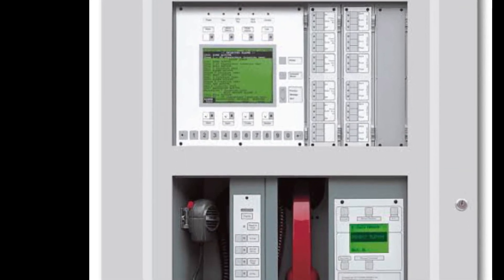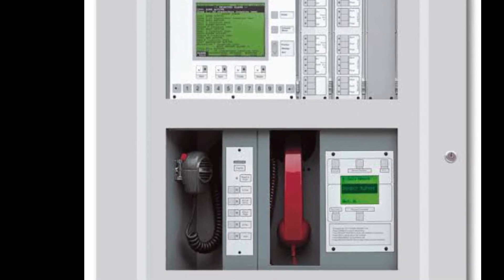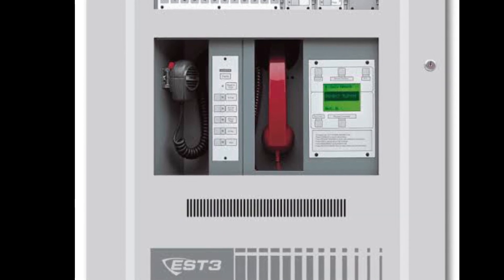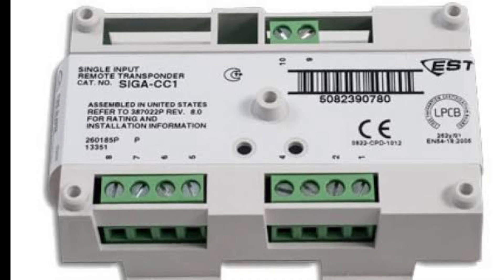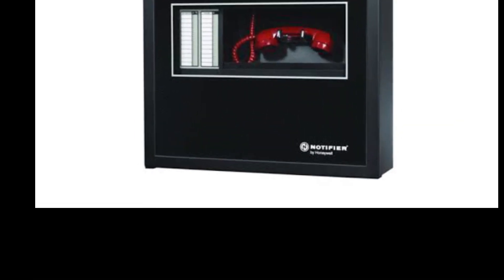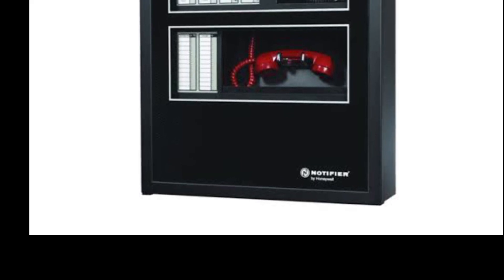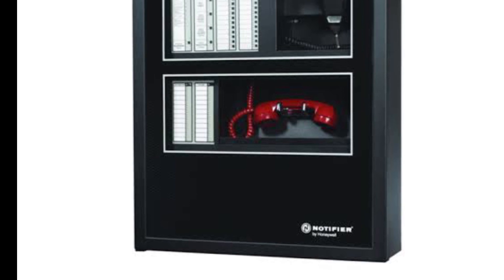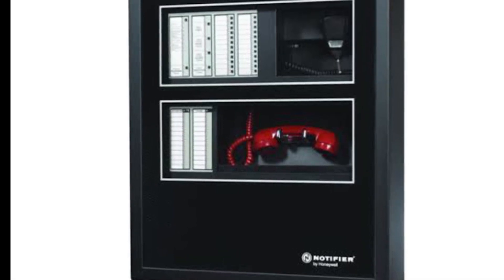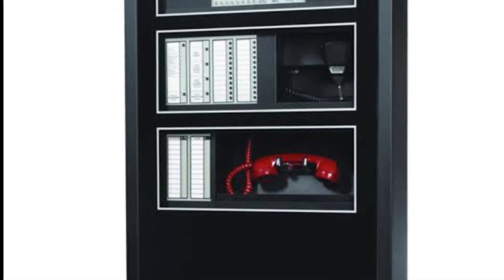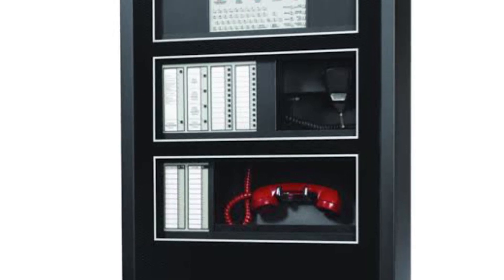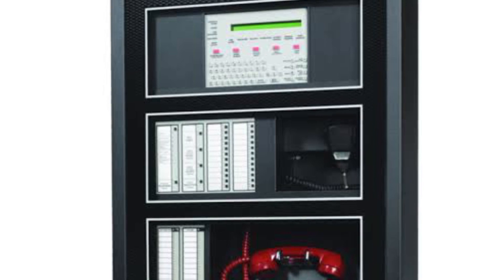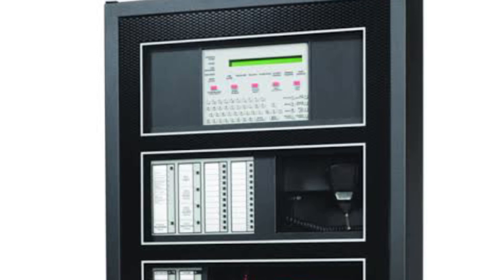If you need to connect two different brand addressable panels — for example, to make a network connecting EST3 to Notifier — here is how. Put a module on the loop of the main panel, such as EST3, and then take from that module's input interface and connect it to the other panel. So if there is an alarm in the Notifier, you can also receive it in the EST3. In this way, using an interface module, monitor module, or input module, you can connect two different brand panels into one network.